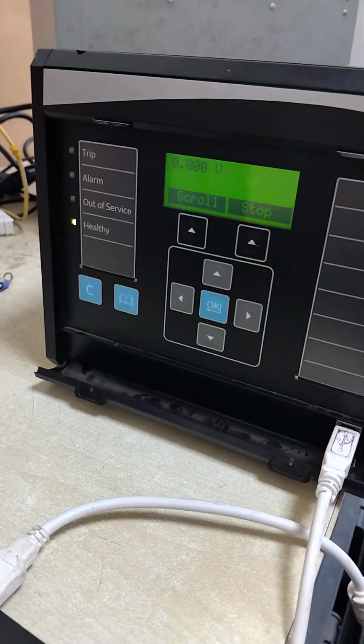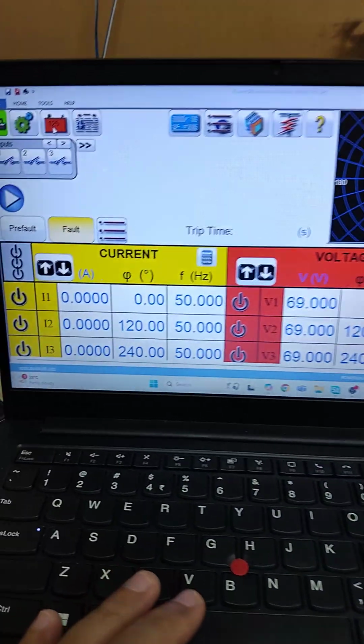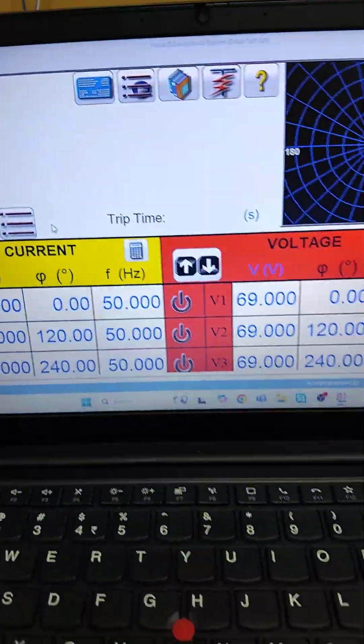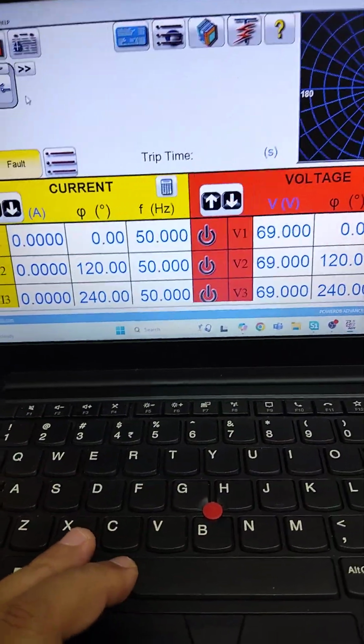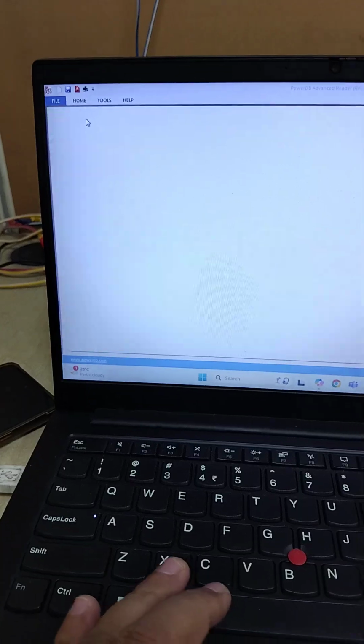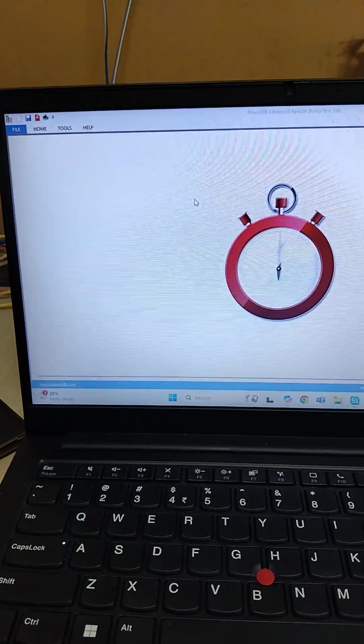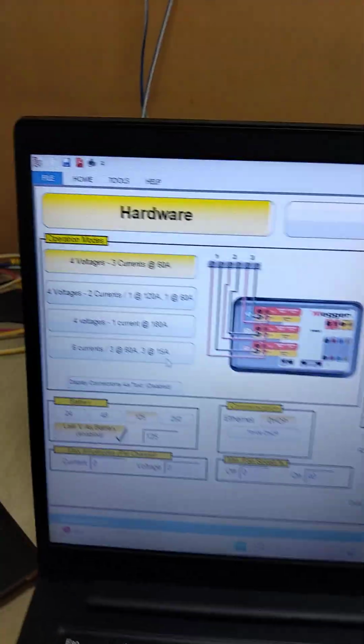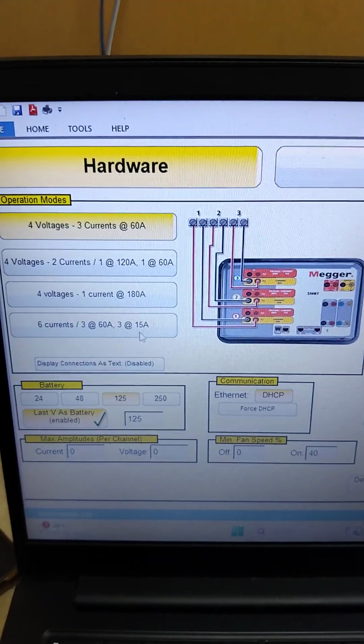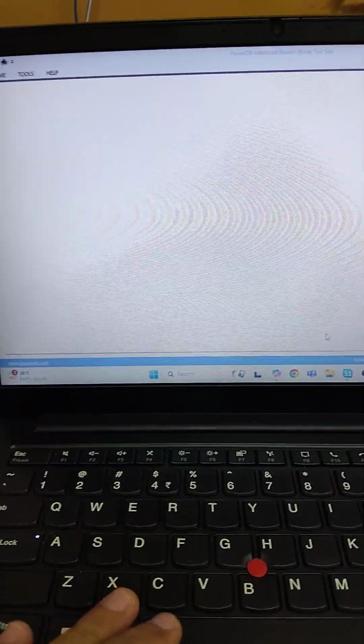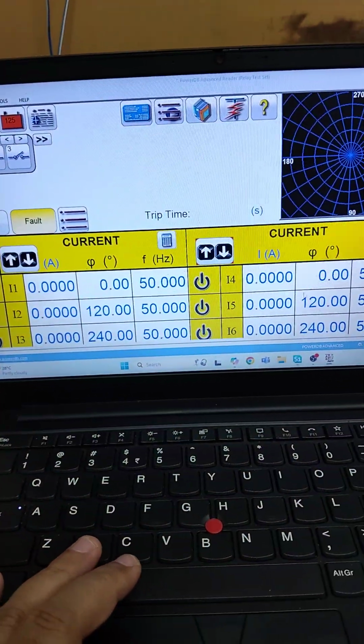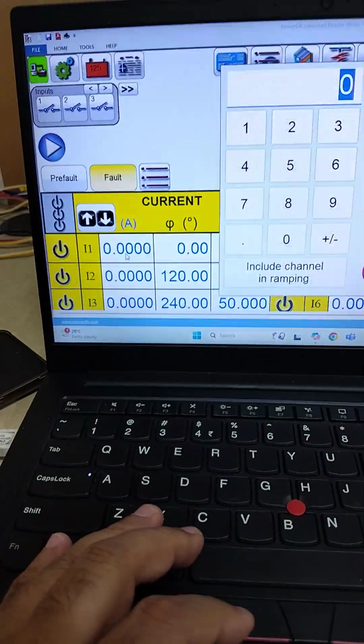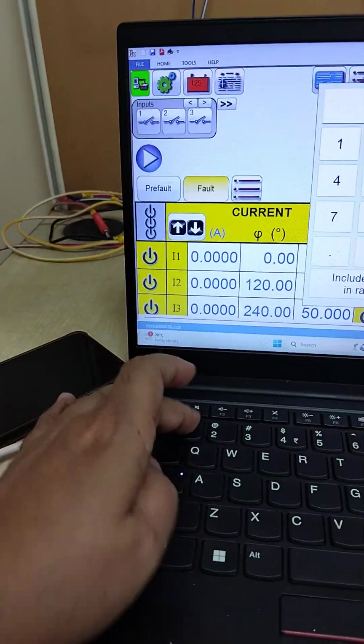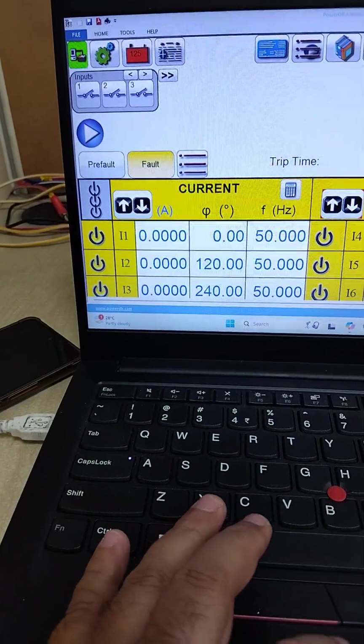Once you get the healthy status on the device, that means the device is powered up completely. So now you can first check the current and voltage injection. For that we need to convert the channels. So here go to hardware, the settings, and select all the 6 current channels, enable it. You can see all the channels here will turn yellow. So now you can inject some minor current to just check whether you are connected perfectly.